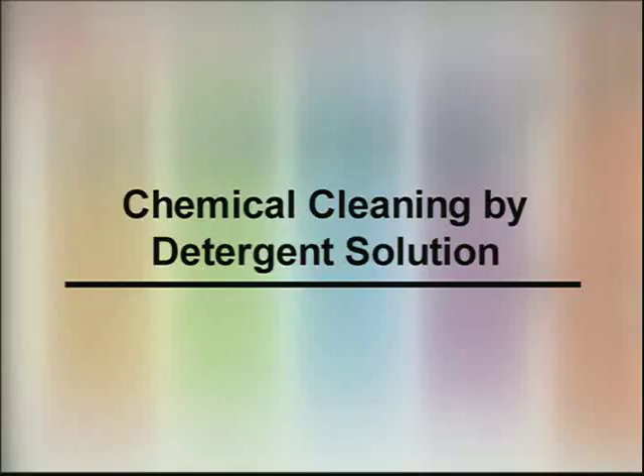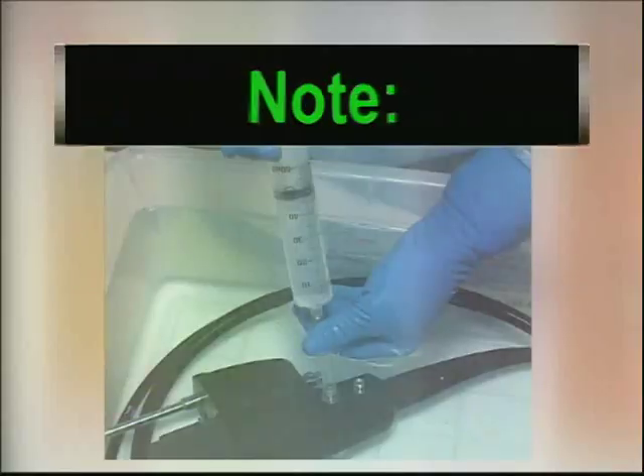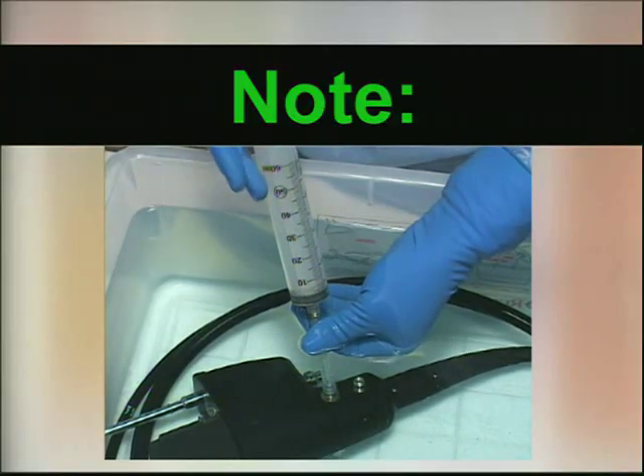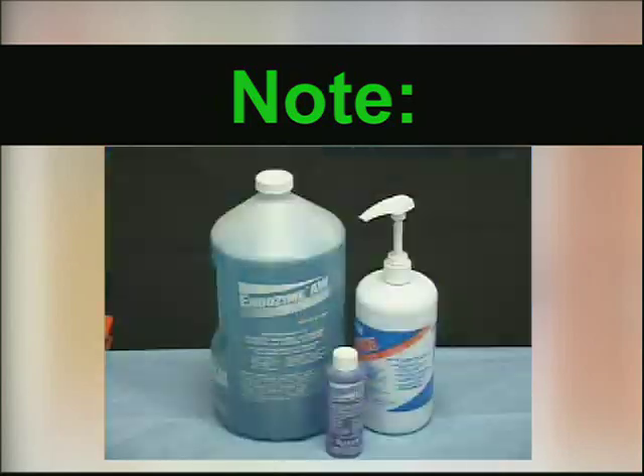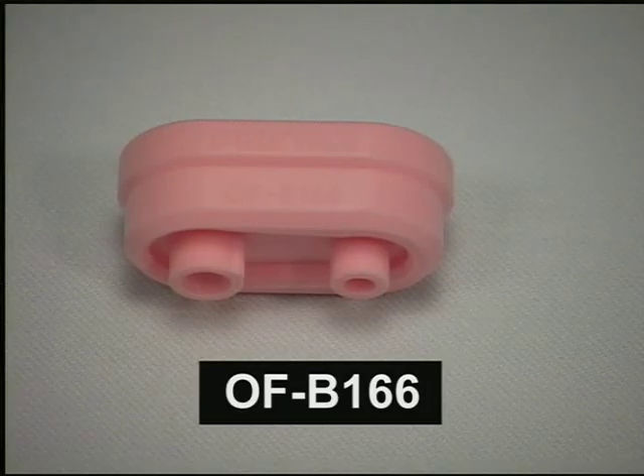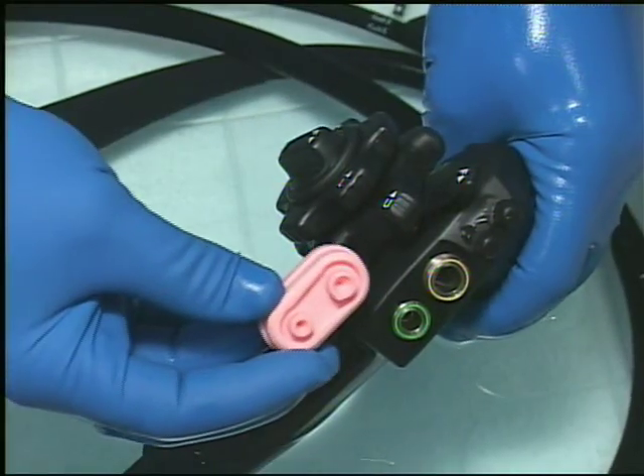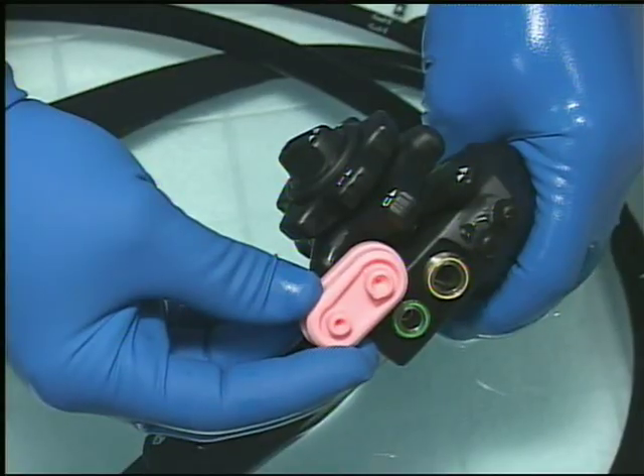Chemical cleaning by detergent solution. Note: brushing of the internal channels is not a substitute for exposure to an appropriate cleaning solution. Manual cleaning by brush complements and augments the cleaning effectiveness of chemical cleaning, for example, enzymatic detergent. The rubber air-water instrument channel cleaning adapter OFB166 should be attached to the air-water cylinder and suction cylinders.